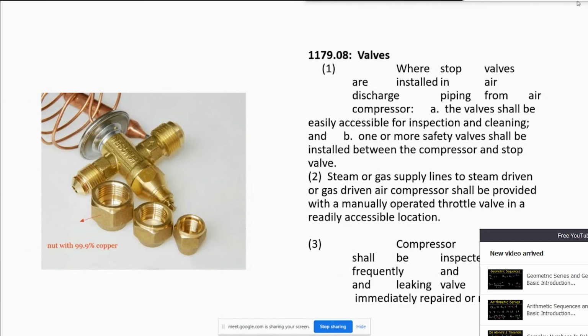Steam or gas supply lines to steam-driven or gas-driven compressors shall be provided with a manually operated throttle valve in a readily accessible location. Compressor valves shall be inspected frequently and regularly, and leaking valves shall be immediately repaired or replaced.